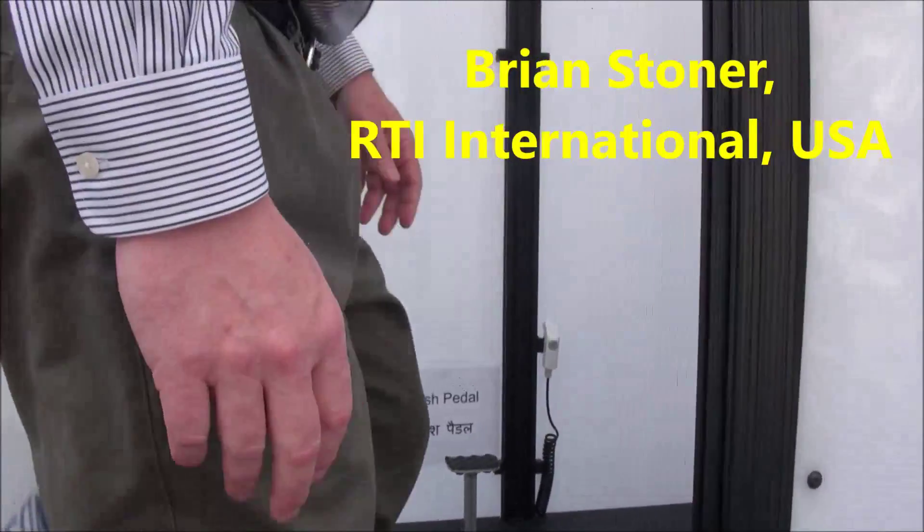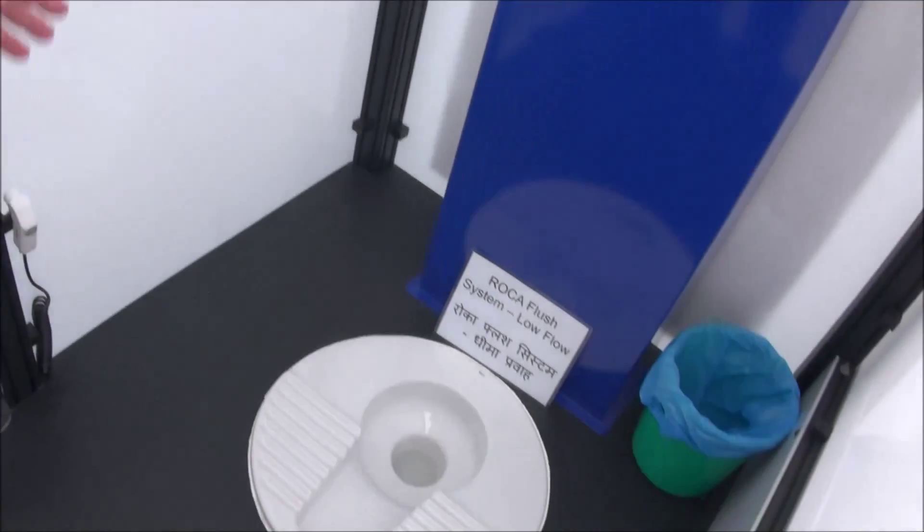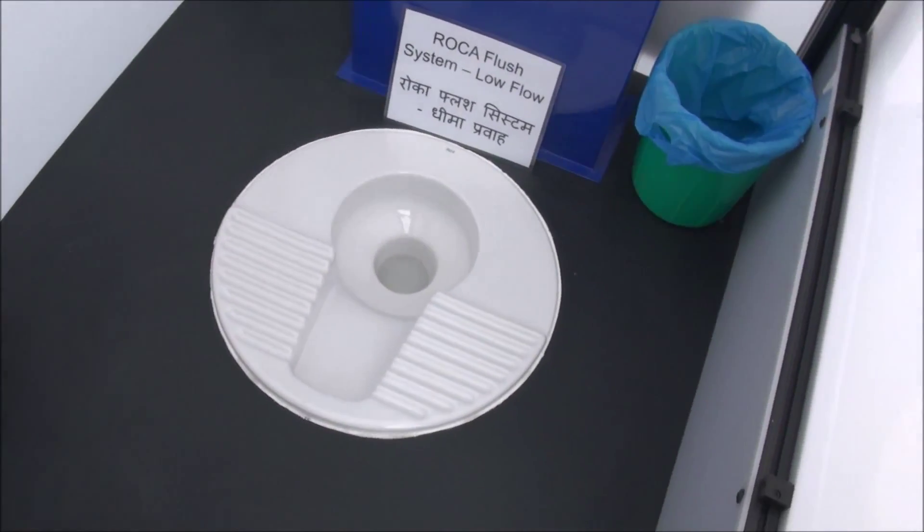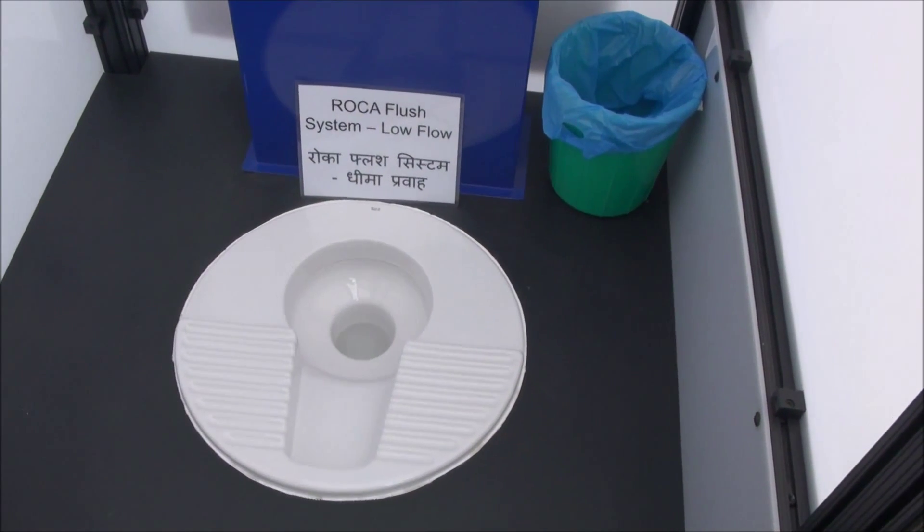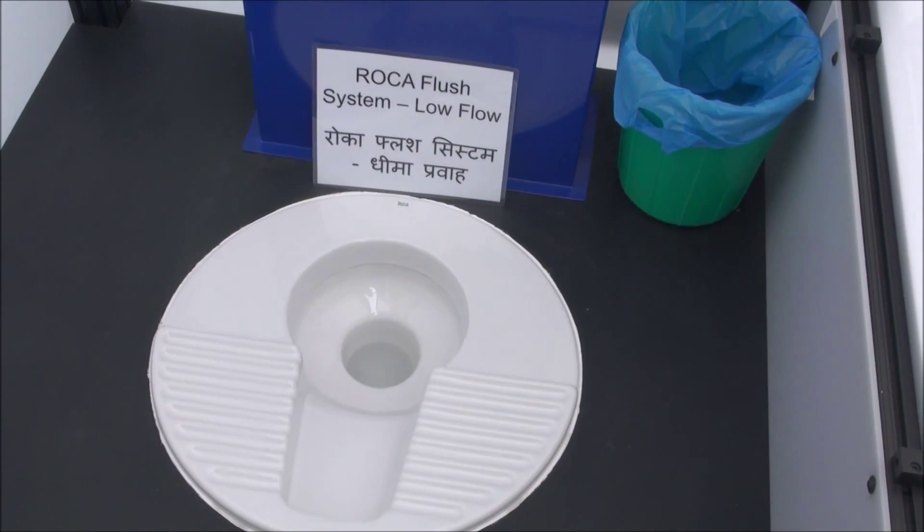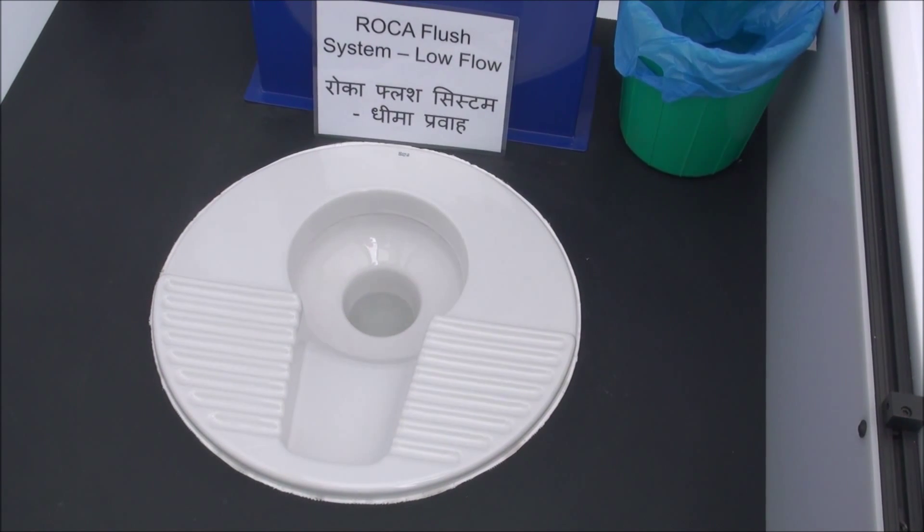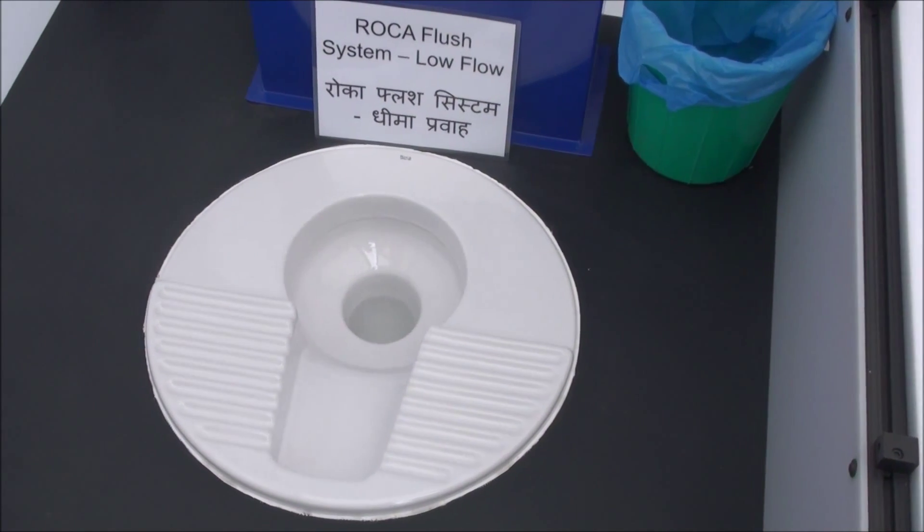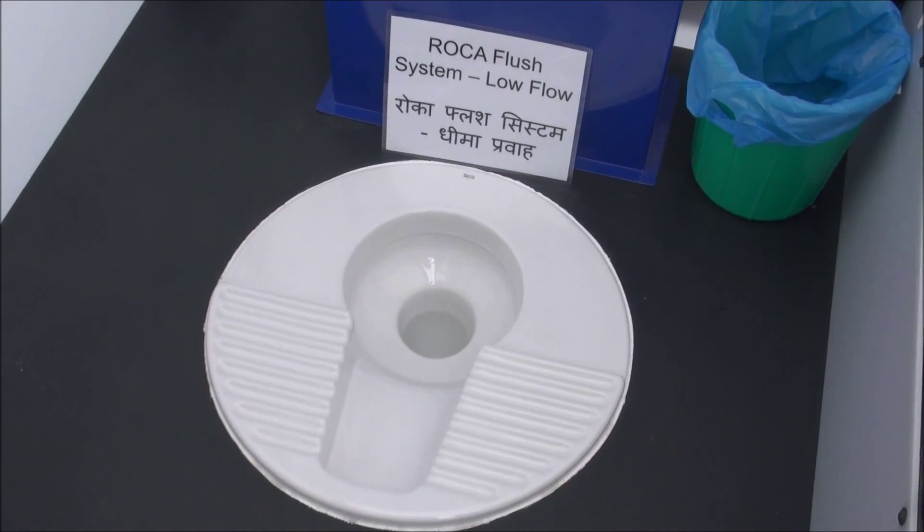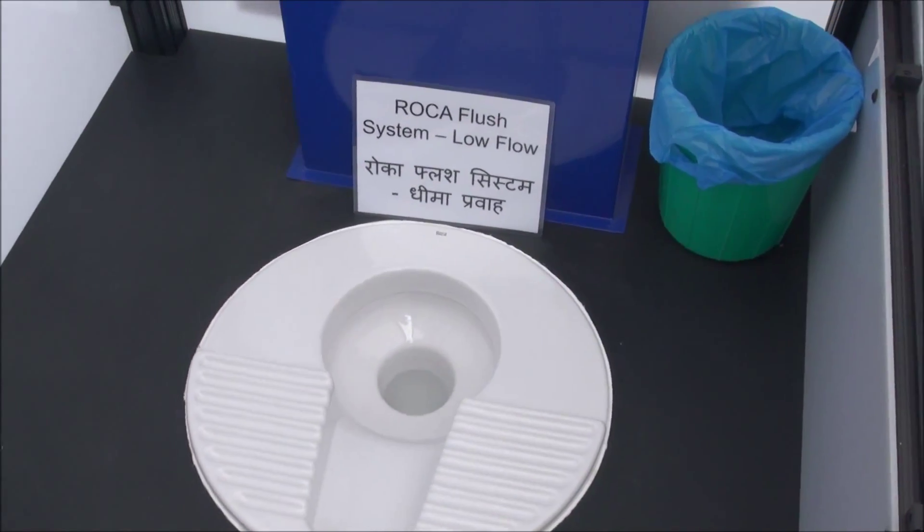We challenged them to develop a plate that did not change the way the user perceived the toilet, but still operates on less than two liters of water. This particular system will operate on 1.5 liters of water. It still maintains a water trap with a standard S-trap, but the fluid dynamic design allows it to effectively flush the liquid.